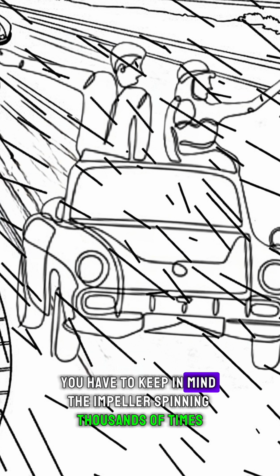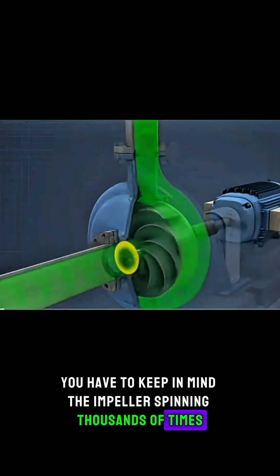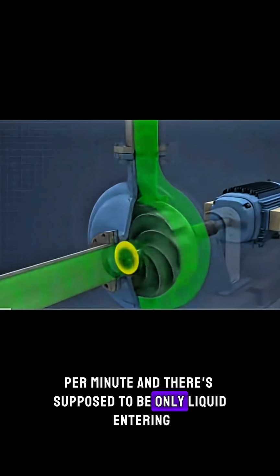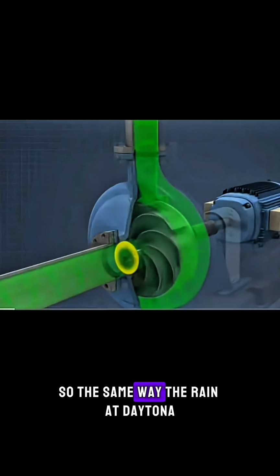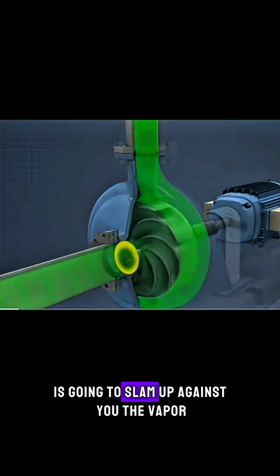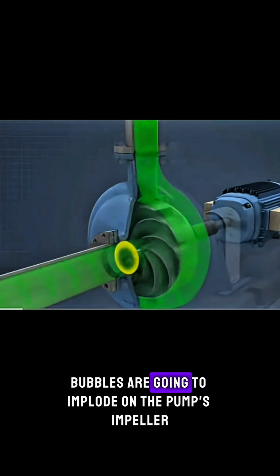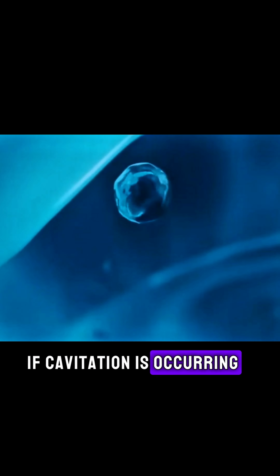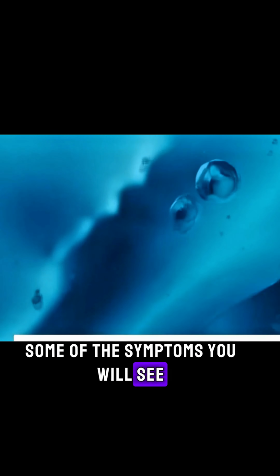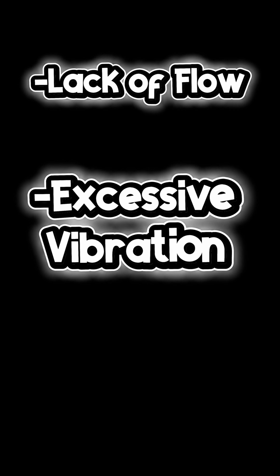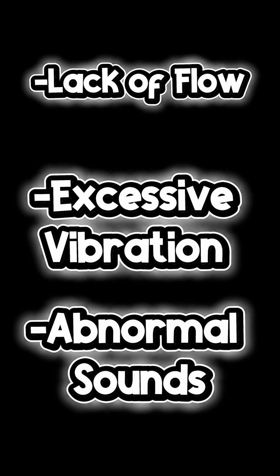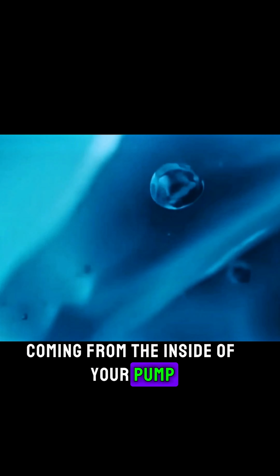You have to keep in mind the impeller is spinning thousands of times per minute and there's supposed to be only liquid entering. So the same way the rain at Daytona is going to slam up against you, the vapor bubbles are going to implode on the pump's impeller. If cavitation is occurring, some of the symptoms you will see are lack of flow, excessive vibration, and abnormal sounds coming from the inside of your pump.